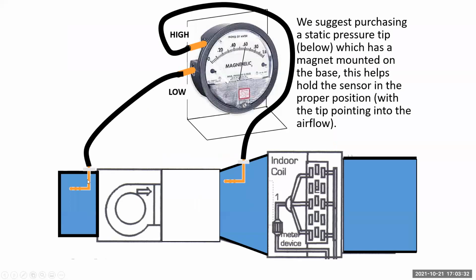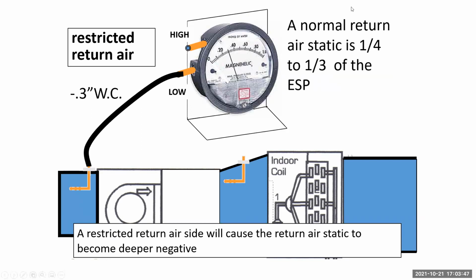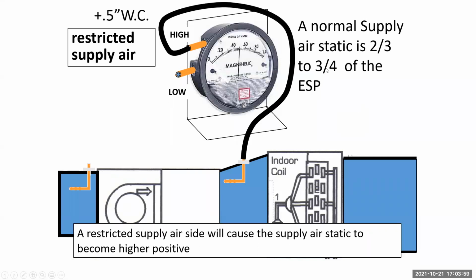I know that with hoses, I said no more than 1/8 inch in unless you're using pitot tips. Once you have pitot tips, you can penetrate that cabinet. You get further down in there, but that's what those are designed for. A normal return is 1/4 to 1/3 of your entire static pressure. Your supply is 2/3 to 3/4 of your complete pressure. If you're backwards, you got big problems.